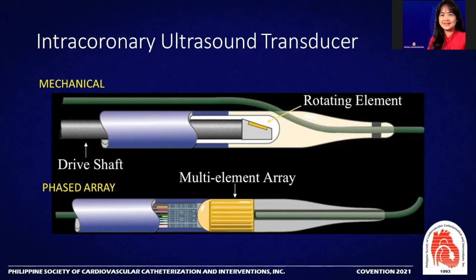The phased array is made up of 64 fixed transducer elements mounted circumferentially around the shaft of the catheter. The guide wire port is located in the center of the transducer, so you won't be able to see the guide wire in the image.